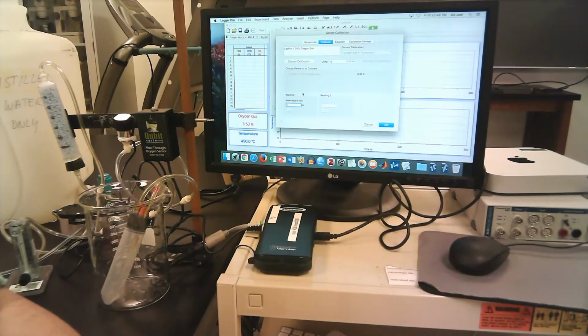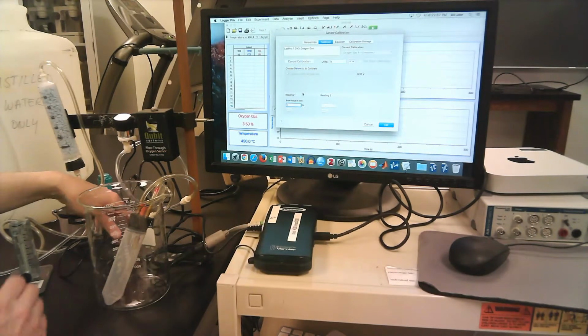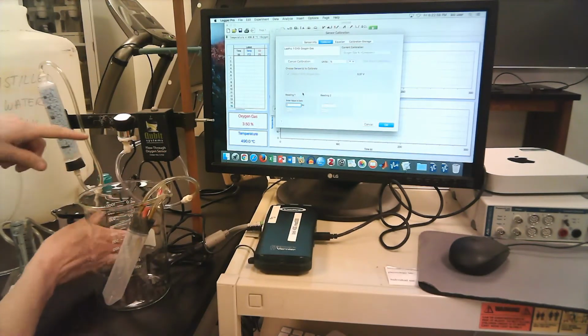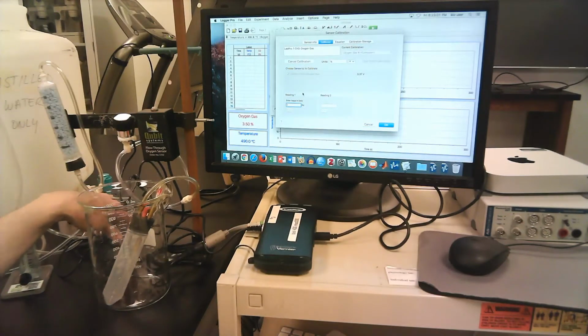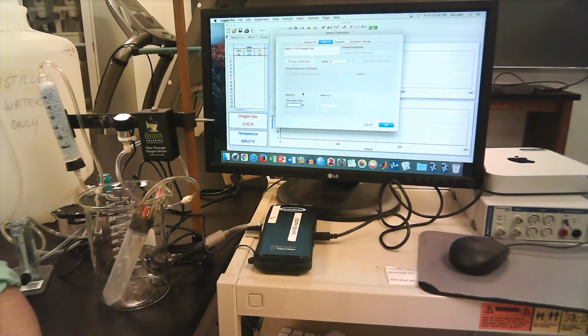There's a fairly long lag time for getting a stable reading. And part of that is because this nitrogen gas has to flow all the way through this whole setup, all the way to the oxygen sensor at the very end of the line, right? So it's going to take a little while to get a stable voltage reading. You want to really wait for a couple of minutes for that voltage reading to get really close to zero, or at least to a very stable measurement, okay?